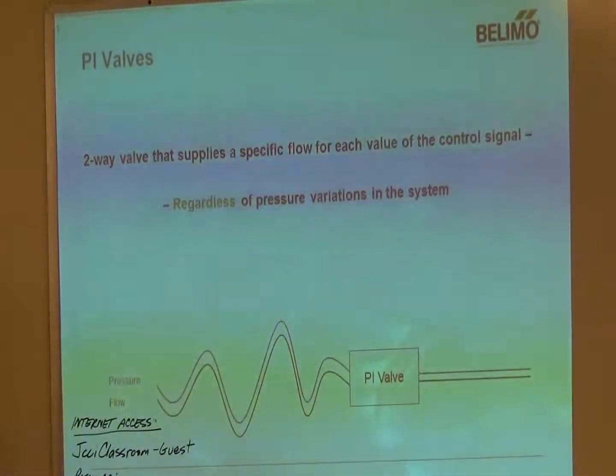Pressure independent valves are two-way valves, and they're two-way because you have to be able to sense inlet and outlet pressure. And they're pressure independent regardless of pressure variations in the system. So you're going to maintain a constant flow for each position of your control valve. Control signal, I'm sorry. Yep, control signal, which is of course going to position the valve in a certain place each time. Say it again, please. You're going to achieve what now? You're going to get a specific flow for each value of your control signal.